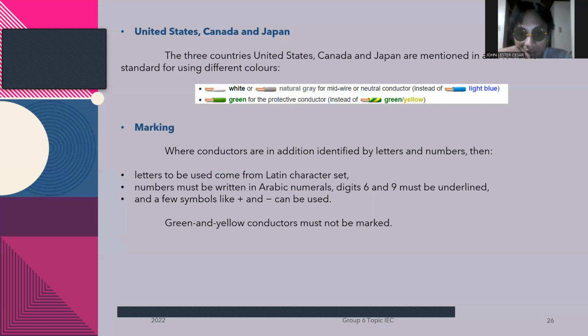Marking: where conductors are in addition identified by letters and numbers, then the letters to be used come from the Latin character set. The numbers must be written in Arabic numerals. Digits 6 and 9 must be underlined, and a few symbols like addition and subtraction can be used. Green and yellow conductors must not be marked.